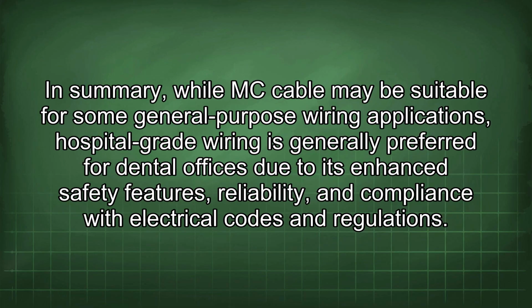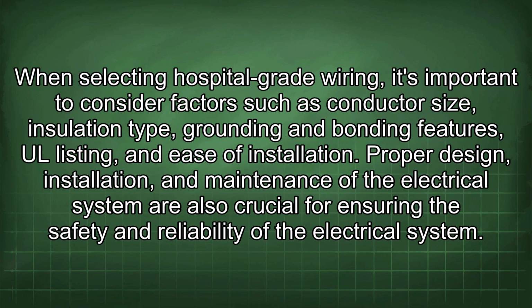In summary, while MC cable may be suitable for some general-purpose wiring applications, hospital-grade wiring is generally preferred for dental offices due to its enhanced safety features, reliability, and compliance with electrical codes and regulations. When selecting hospital-grade wiring, it's important to consider factors such as conductor size, insulation type, grounding and bonding features, UL listing, and ease of installation.